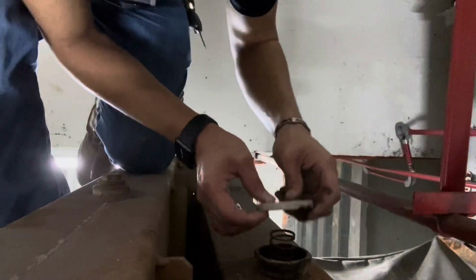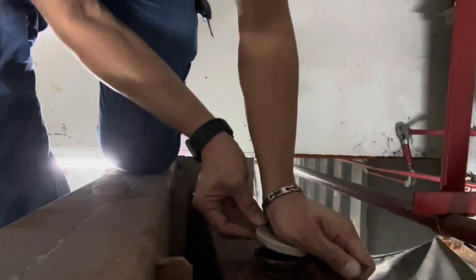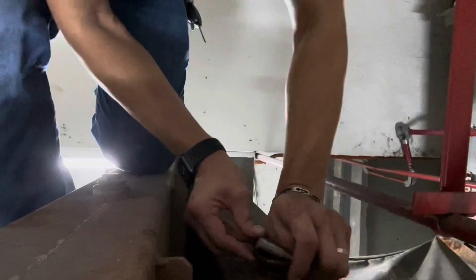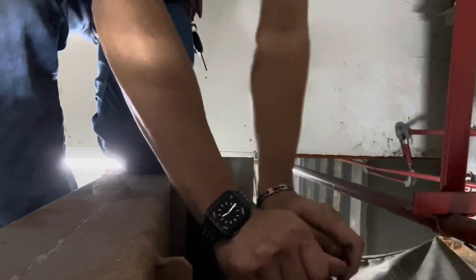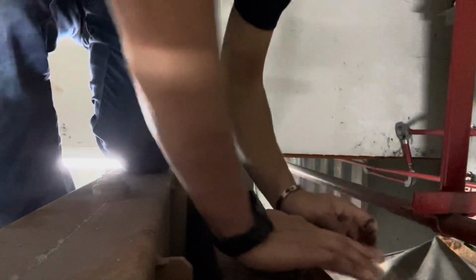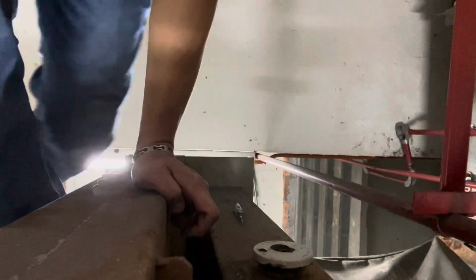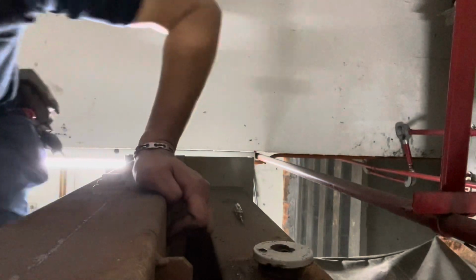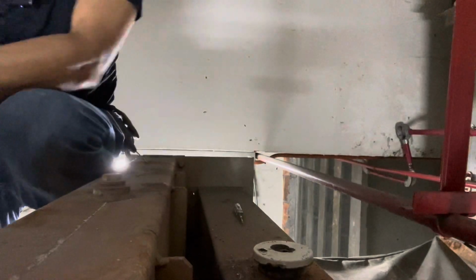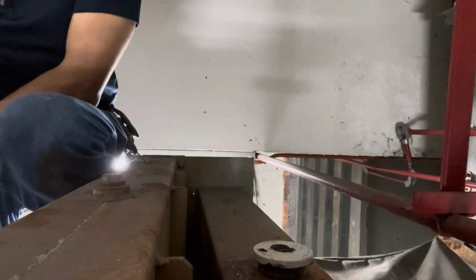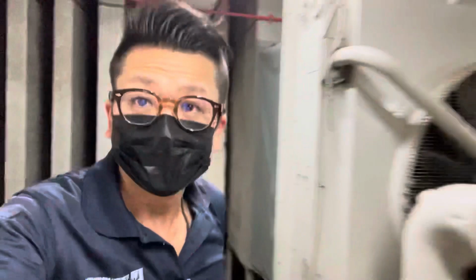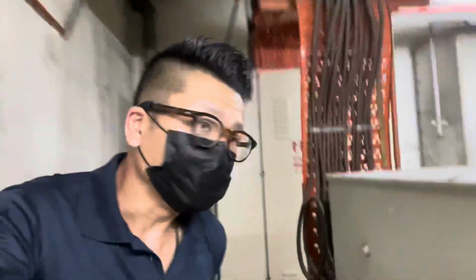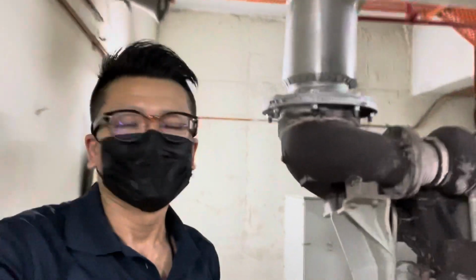If I'm not able to close this thing, any power interruption, the genset runs, and as the temperature builds up, water will spill. So however faulty it is, I must close it back. Alright. As long as it serves the purpose. So be it. Alright, after we have checked the parameters, later we will test run the genset remotely from the ATS panel. Okay, there's plenty of defects here, so we'll have to advise the site person in charge to get it rectified.